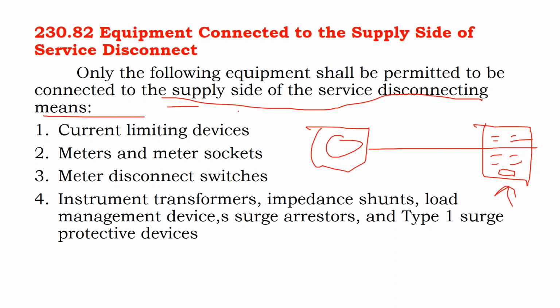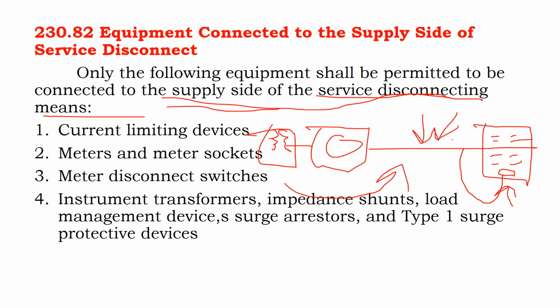And so connections to the supply side of the service are not on the utility side where you have your transformer and your power lines, but this section right here is considered to be on the supply side of your electric service main disconnecting means. So this is actually going up through the main disconnecting means. This is the supply side of the main disconnecting means. And in the solar industry, we talk about supply side taps rather than load side taps, where you can connect a solar array or a battery bank or a generator protecting a critical load panel on the bottom of that bus bar, or you can connect it up to 100% of your electric service on the supply side connection.